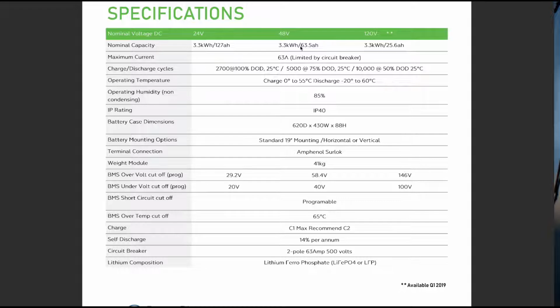Now, how do we work out how many kilowatt hours our previous system was? So I'll just cut over to that. I said these were 1500 amp hour cells. So that's 1500 amp hours times the string voltage, which is 48, times the number of strings, which is 2. And what do you know? I'm actually going to have to get my calculator out. I really should have done this beforehand, but here we go. It's always fun to do these things live. So 1500 times 48 times 2 equals 144,000 watt hours. And if we divide that by 1,000, it's 144 kilowatt hours.